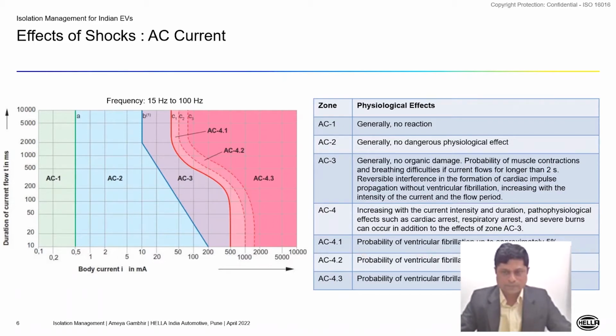So there's a 5% possibility, 50% possibility, and then more than 50% possibility of ventricular fibrillation, which in other words means possible death. So all said and done, we should be playing in the green zone. This is where the isolation management system should give us an alarm if the leakage currents we are talking about cross from AC1 to AC2, or more dangerously, from AC2 to AC3.